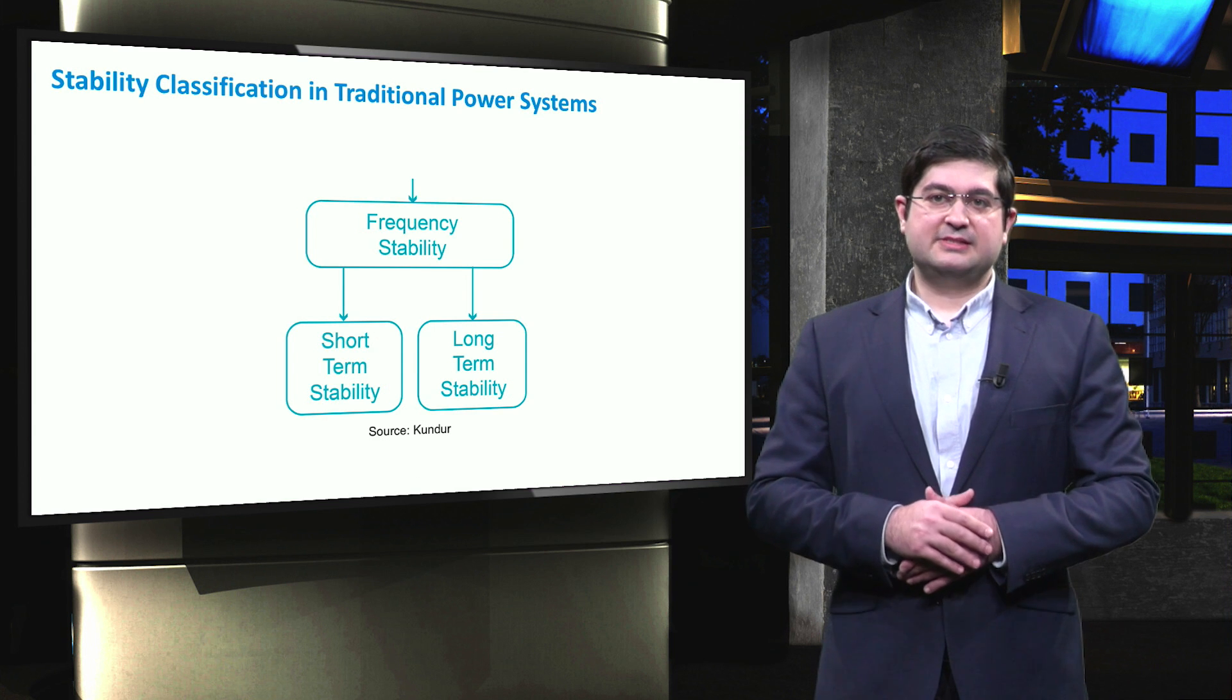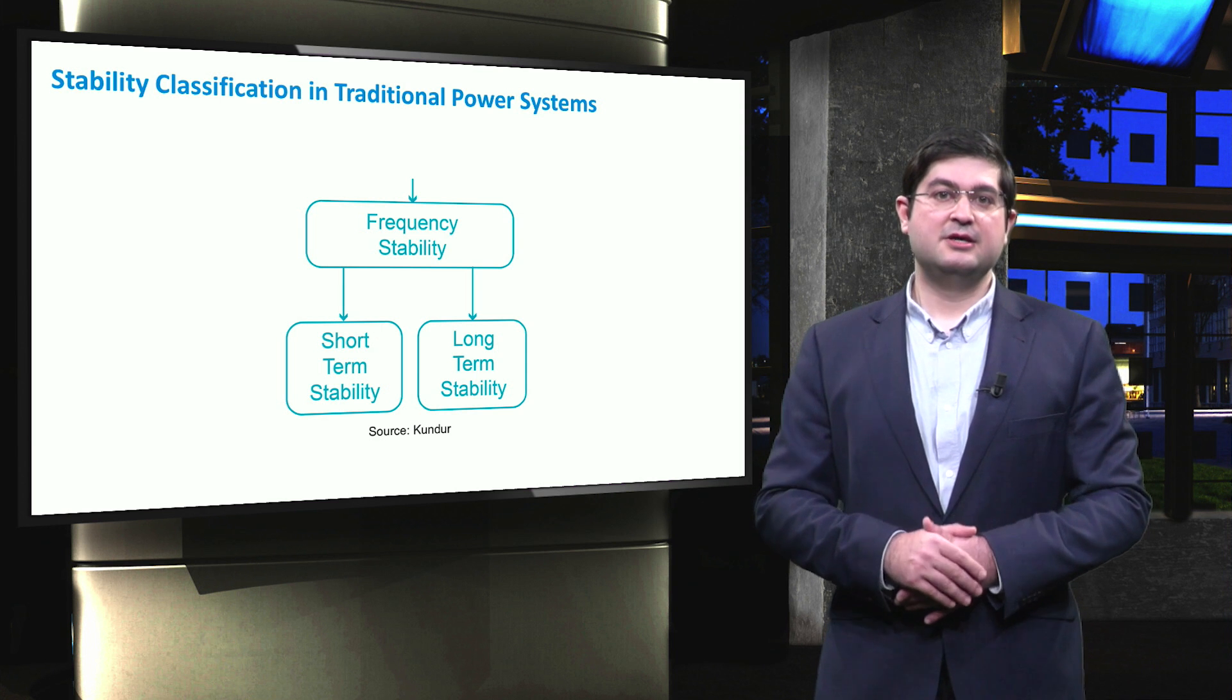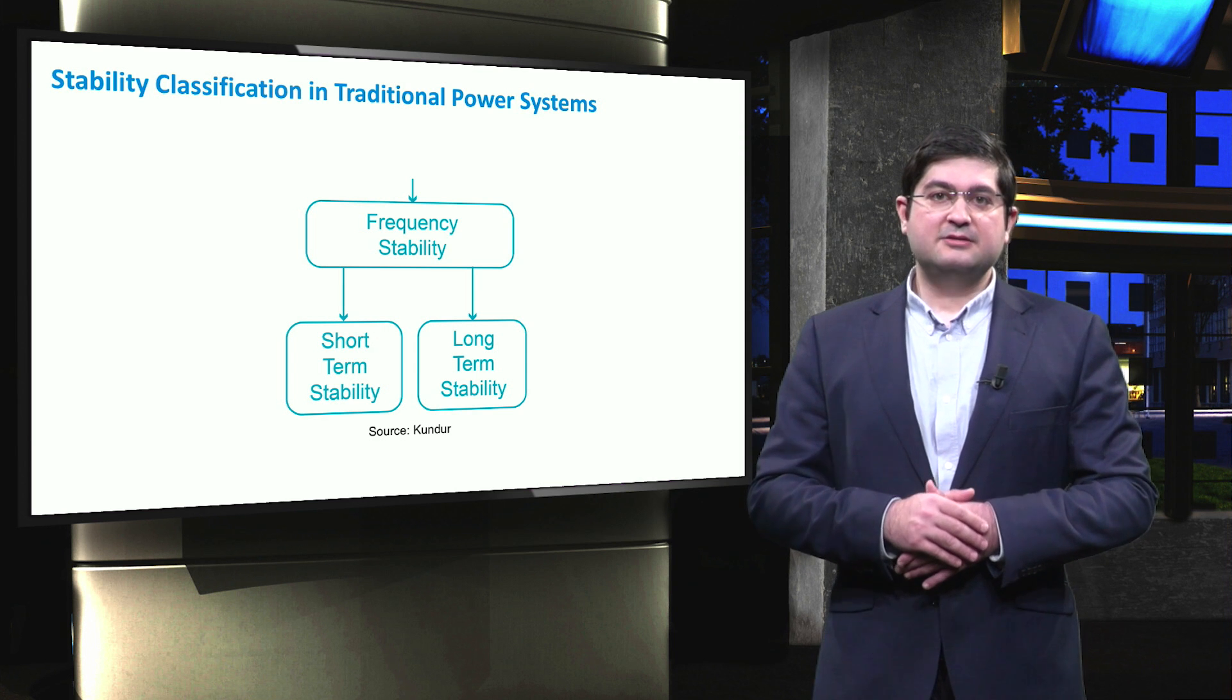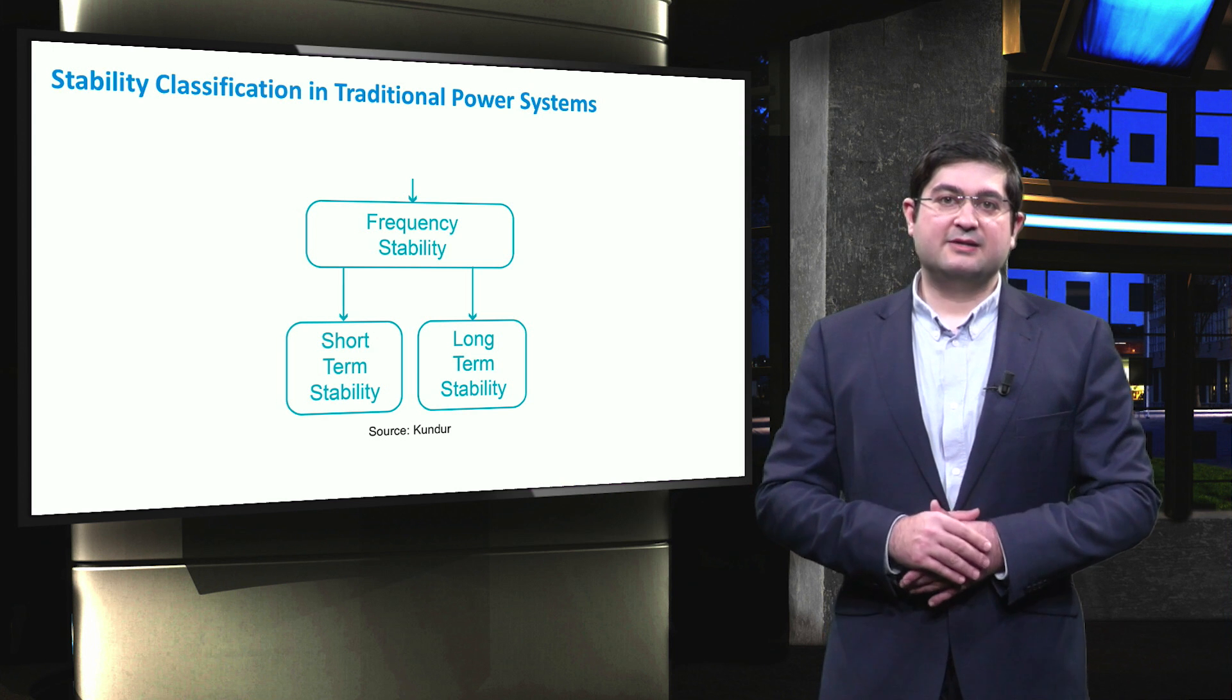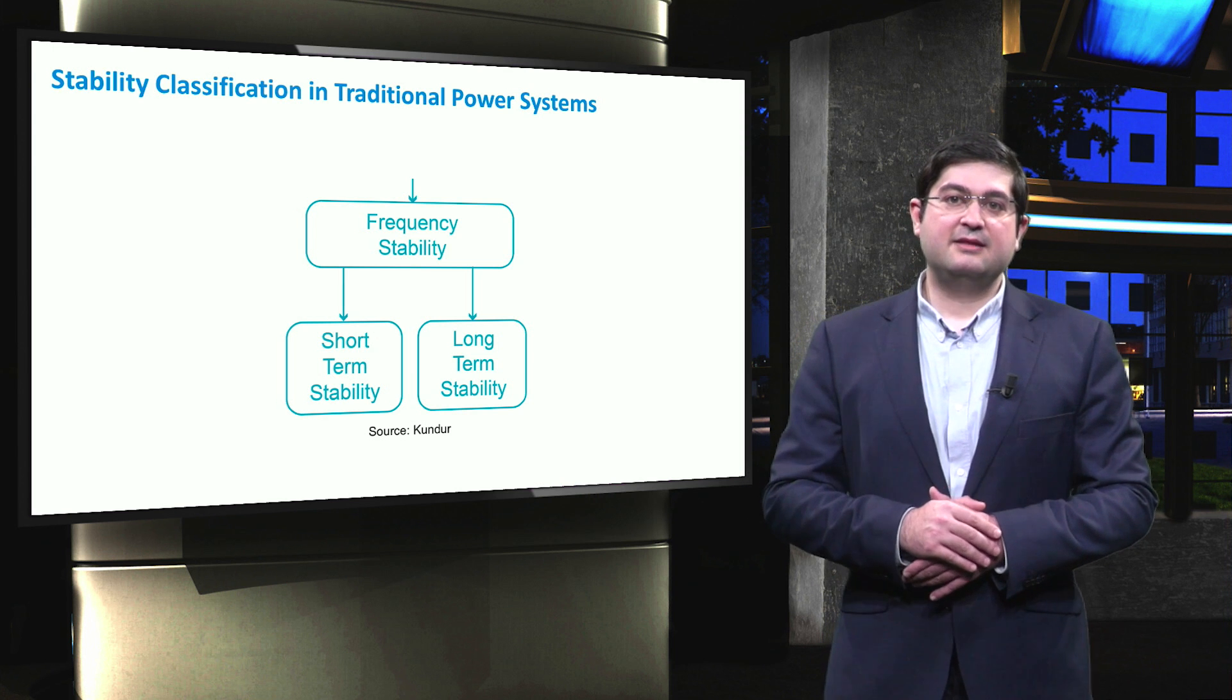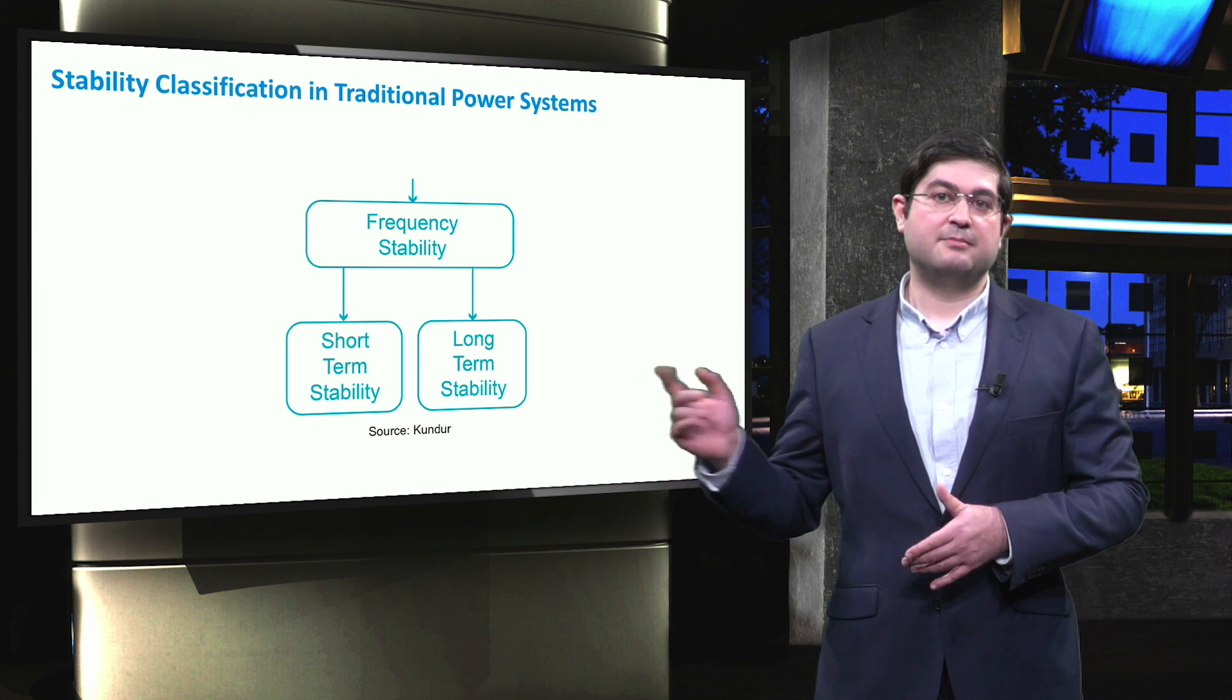Frequency stability can be considered for both short time scale within several seconds or long time scale within several minutes up to hours. In electric power systems, ideally speaking, active power balance between the power produced by generating units and the electrical demand must be instantaneously maintained and satisfied for both short and long time scales.